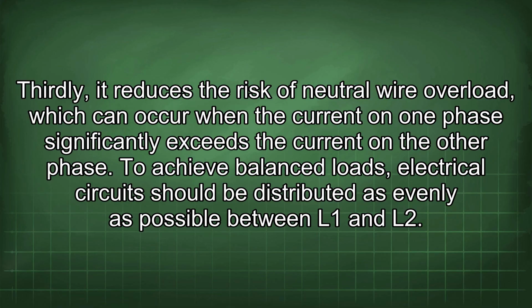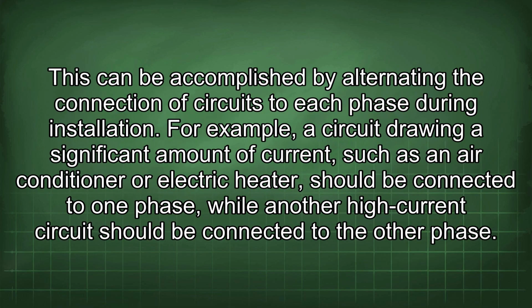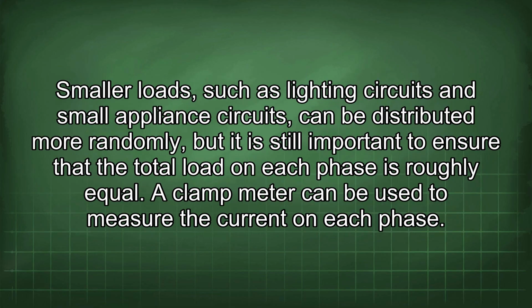To achieve balanced loads, electrical circuits should be distributed as evenly as possible between L1 and L2. This can be accomplished by alternating the connection of circuits to each phase during installation. For example, a circuit drawing a significant amount of current, such as an air conditioner or electric heater, should be connected to one phase, while another high current circuit should be connected to the other phase. Smaller loads, such as lighting circuits and small appliance circuits, can be distributed more randomly, but it is still important to ensure that the total load on each phase is roughly equal.